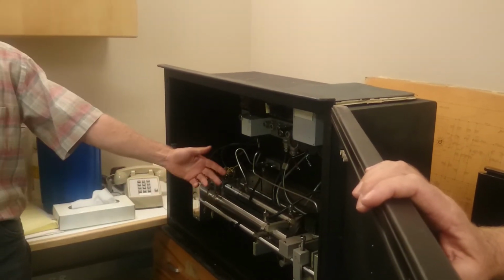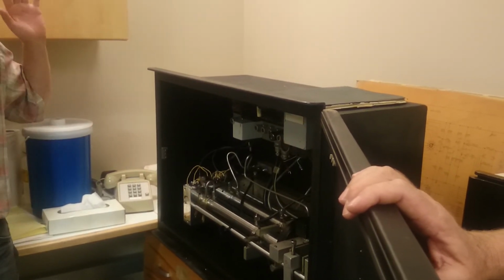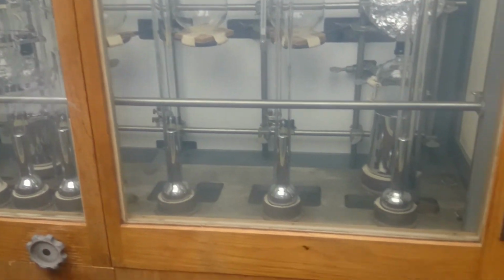I should say that the techniques for measuring carbon dioxide today, now by a much larger community, involve a standards lab that does calibration, that disseminates tanks, and then the individuals measure almost entirely with infrared analyzers. Now there's a tendency to use laser methods rather than non-dispersive analyzers. But there's still a lot of these in use, and they're very rugged and simple. It's a 1950s measurement principle, but it's not going away.